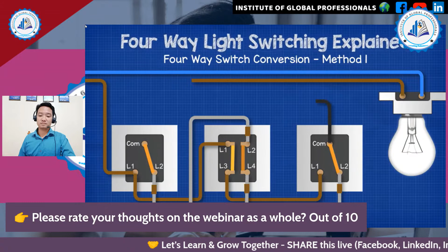We run a grey wire from L2 of switch 3 to L4 of switch 2, placing a brown sleeve on the wires to indicate it is intermittently live. We run another grey wire from L2 of switch 2 to L2 of switch 1, then join the two end switches with a black wire to each common, and connect the blue wire from L2 of switch 1 to the light circuit.